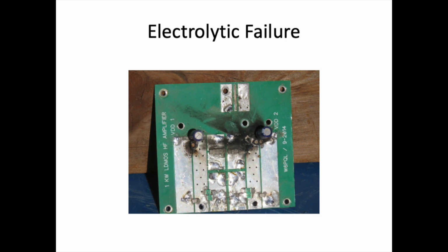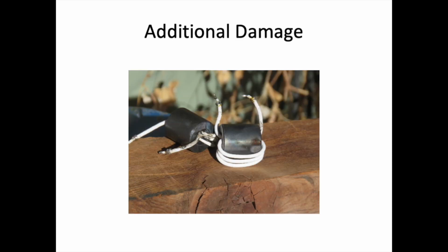Actually I was using a couple of modules, and the two modules was really a poor idea with the balancing loads and everything else. Essentially a single module puts out 1200 watts, and because of the third harmonic coming back from the filters, with two modules you may get 1400 watts. So the difference of 200 watts is not worth it at that point. So again, I went back to a single module, and I had a spare.